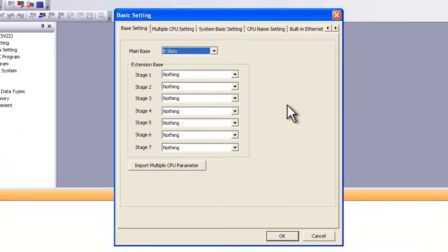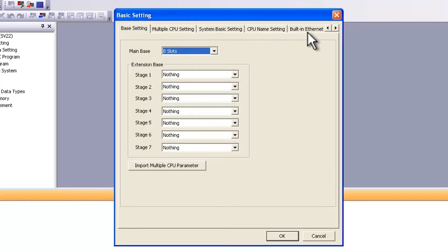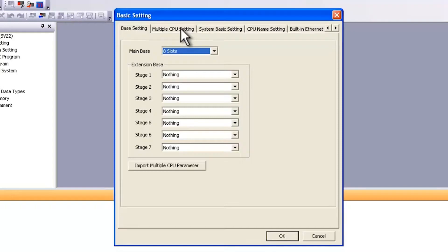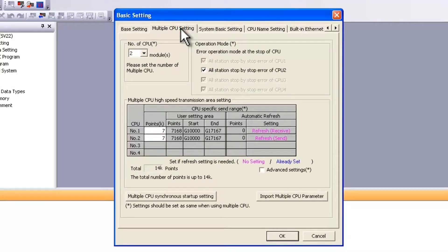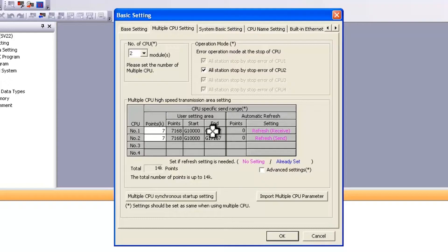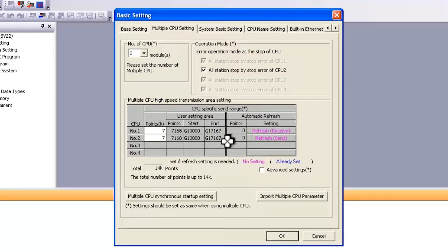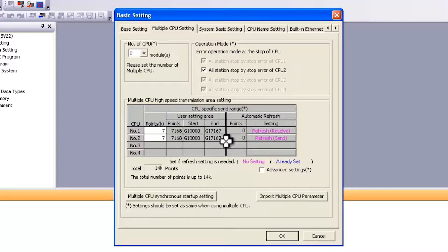Now these are the basic settings. It's a good idea to go through these tabs and have an understanding of what's in each one of them. Most importantly, make sure that your multiple CPU settings are matching those in the PLC. More details on memory sharing between multiple CPUs in a Mitsubishi system can be found in another Quick Tips video.